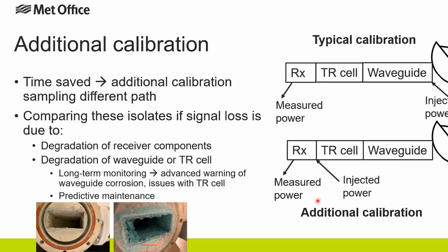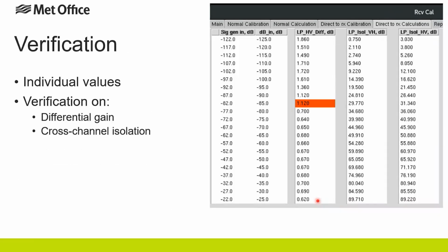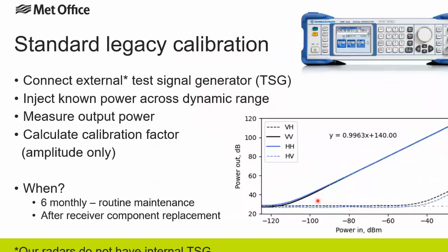You said that you're using traditional signal generators in calibration. Do you have site-specific signal generators for all sites, or do you carry them around, and how often do you calibrate the signal generators? Yes, the test generators will be with each service centre. Our field service engineers would carry them to site. And they're calibrated on the manufacturer's schedule, which I think is every 3 years.